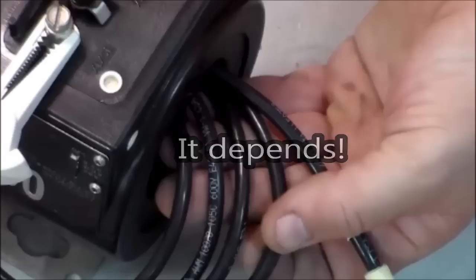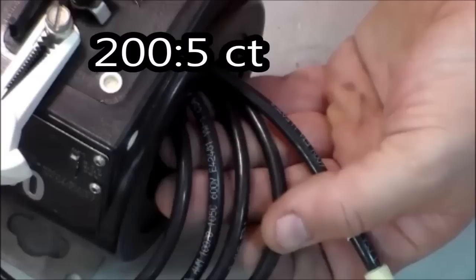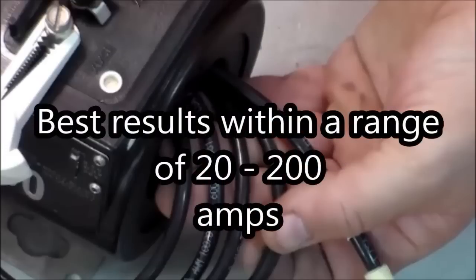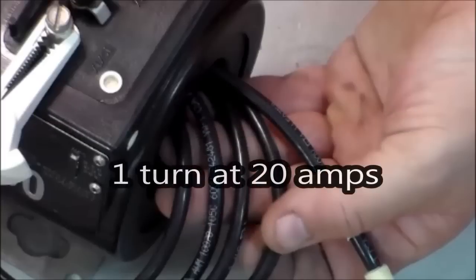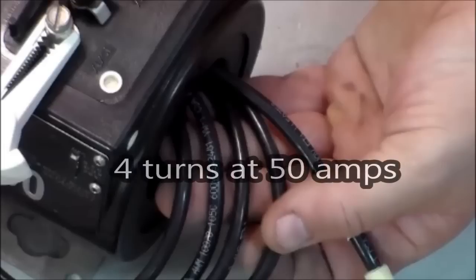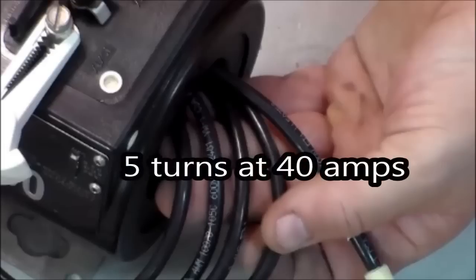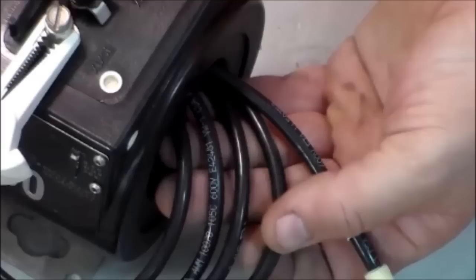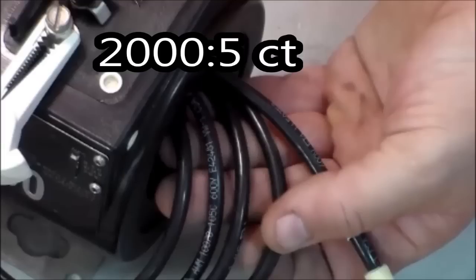It depends. Let's start by looking at a 200 to 5 CT. We'll always see the best test results if we stay within a CT's window of accuracy. And for a 200 amp CT, that would be roughly between 20 and 200 amps. We could accomplish the minimum with 1 turn and only 20 amps. But we'll get a better test if we pick a turns ratio and amp combination that will result in roughly the nameplate current.